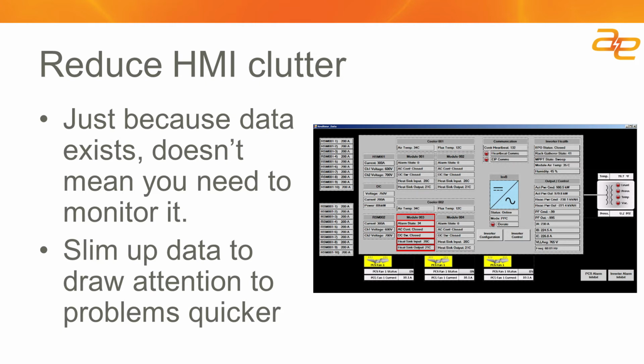Just because data exists doesn't mean it needs to be on the screen. We've got a sample here of an inverter screen I use frequently, where there's a whole lot of data but not a whole lot of information. There's too much clutter on the screen to know whether the inverter is working well, and it can be 10 times worse with a tracker system. If you boil down to just the valuable points that help you figure out where the problems are, it makes the system more valuable, and you'll spend less time finding problems that'll jump right out at you.